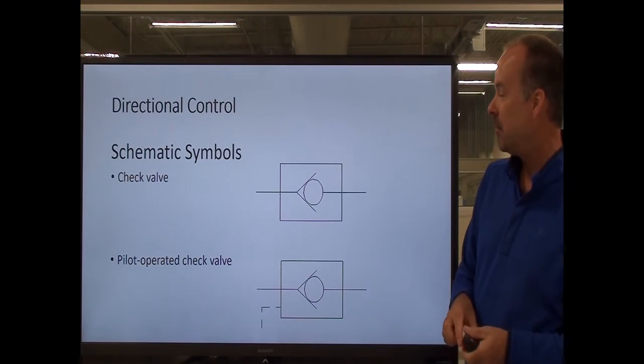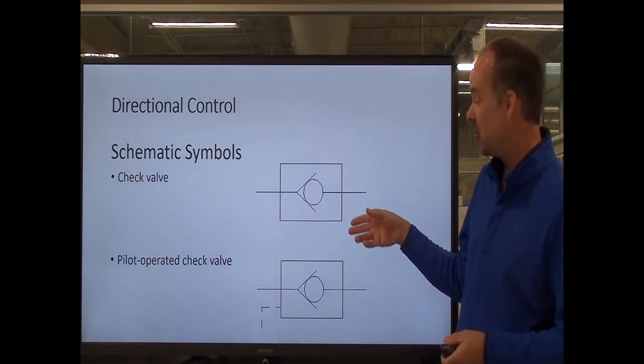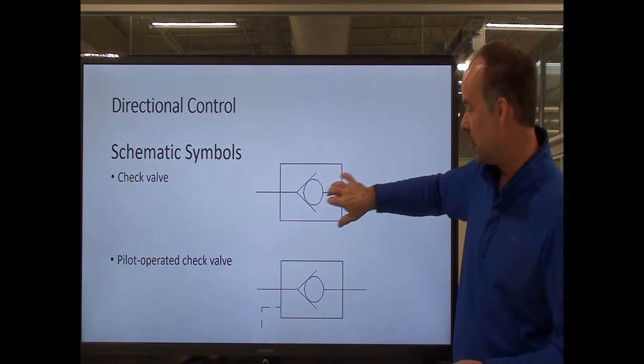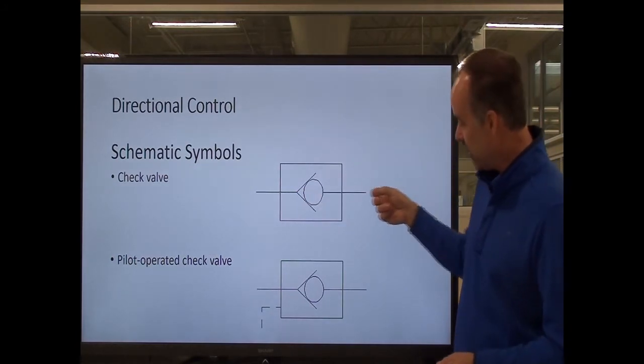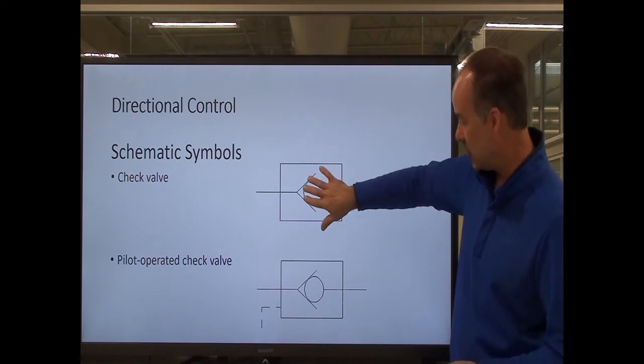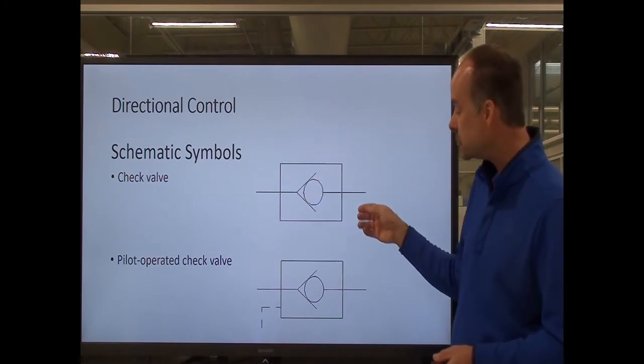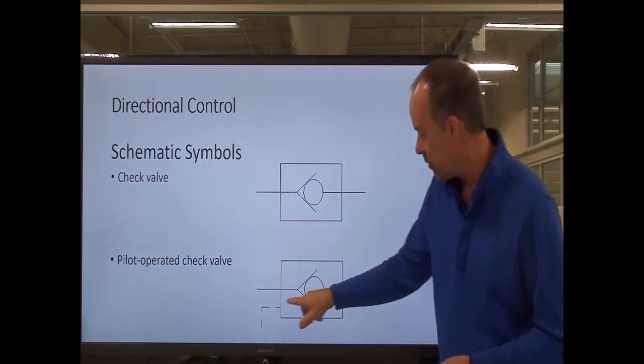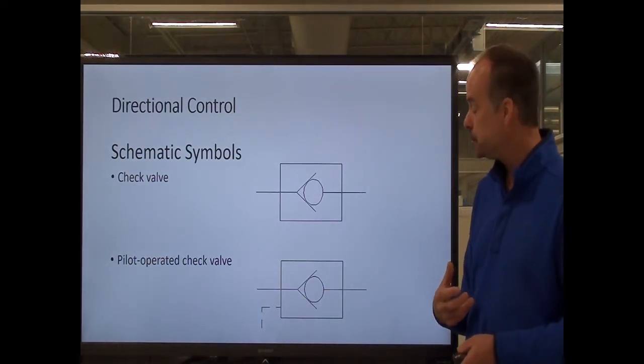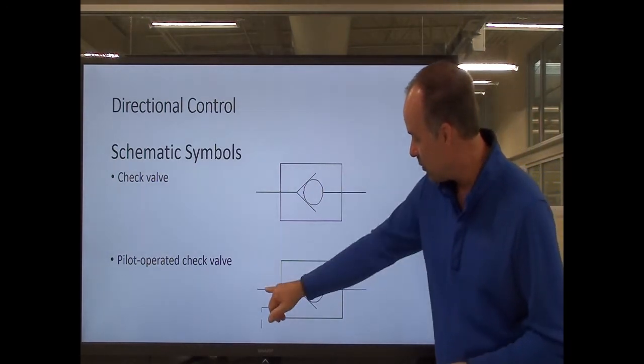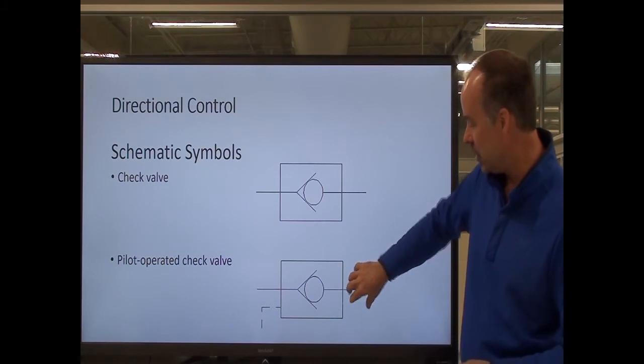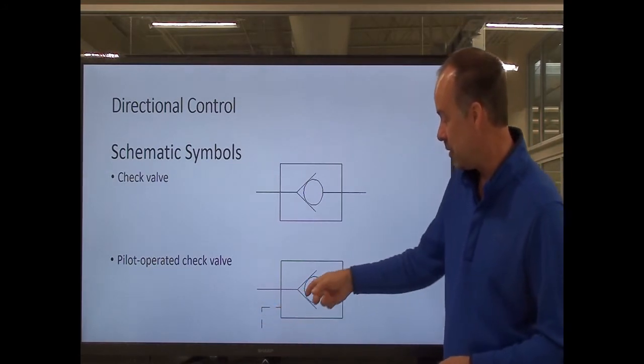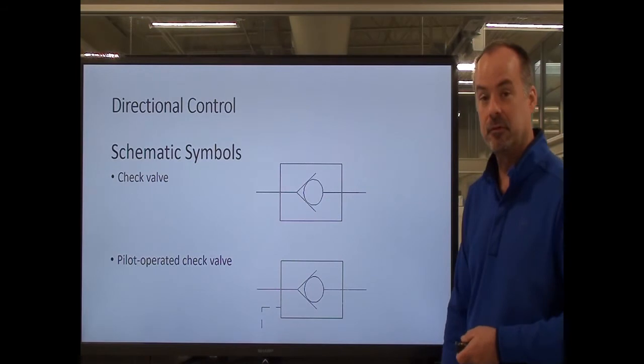The schematic symbol for a check valve is a very good representation of what's actually going on inside. This check valve will allow flow in one direction — pressure pushes the ball off the seat and allows fluid to flow that way. Fluid flowing back the other way will push the ball into the seat and seal it off. Down here I have a pilot-operated check valve — the dashed line coming out of the symbol tells me it's pilot-operated. The same rules apply, but if I have pilot pressure, it forces the ball off the seat and allows fluid to flow in that direction.